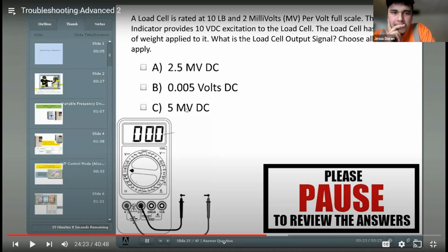Basically the easy way to understand this is, you push 10 pounds on this, you max it out, you get a 20 millivolt output. But if you only put 5 pounds onto it, you're going to get half of the output, so only 10 millivolts. Now we cut it in half again to get to 2.5 pounds. So we cut that 10 in half, and now we're down to 5 millivolt output. That's a quarter of our full output, and we gave that load cell a quarter of its full range. Does that make sense?